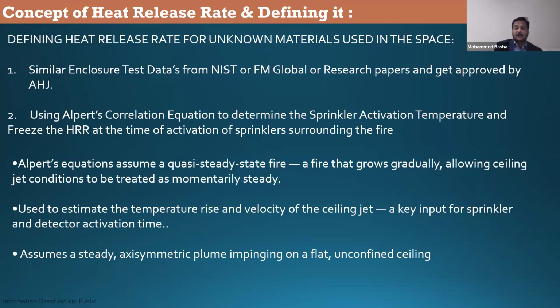I told you about fuel controlled fires and sprinkler controlled fires. Alpert correlations should be used if you have sprinklers in the space. What if you don't have sprinklers in the space? You have to consider a fuel controlled fire.